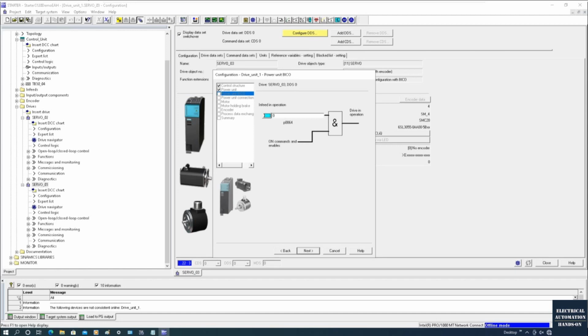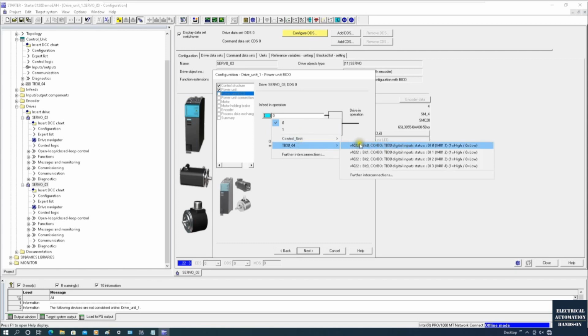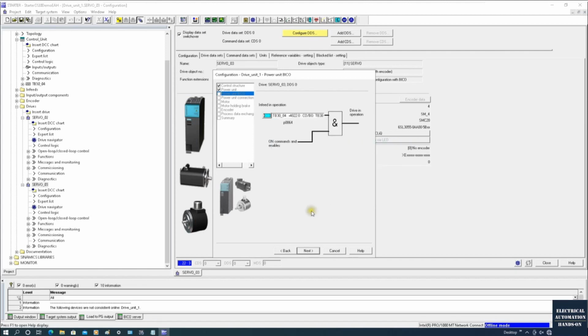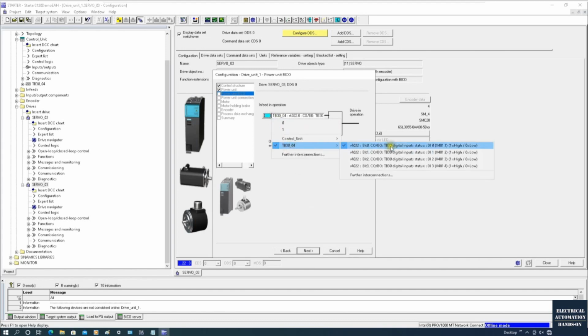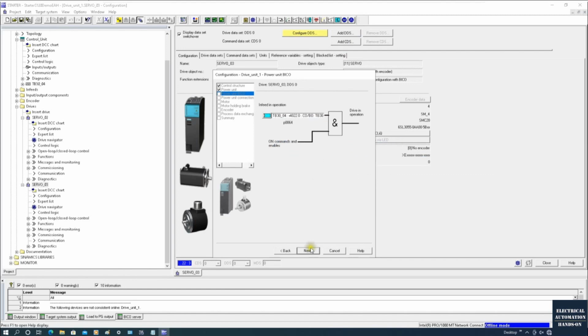For testing purposes, we can set always true here, assuming the in-feed is always ready. Or we can involve the actual in-feed ready signal. In this demo, it's using one of the signals from the TB30. That signal channel comes from R4022.0. Once the in-feed is ready, we can use this signal as one of the conditions to enable the drive. That makes sure if the in-feed module has something wrong, we cannot enable the drive.